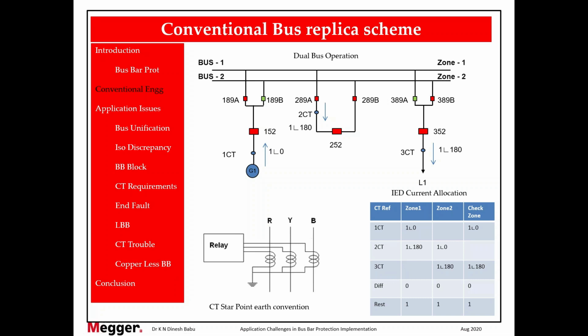Now whatever we discussed is repeated for all the bays. So even if you have 40 CTs here, 1 CT, 2 CT, 3 CT, 4 CT, 5 CT, etc. up to 40, the same logic applies. Even if you have a number of busbars, say 2 main 1 transfer, 3 bus, you will simply have zone 1, zone 2, another zone 3 and check zone. Another column would be added, but the same logic applies. Okay, now whatever we discussed is the same fundamental.